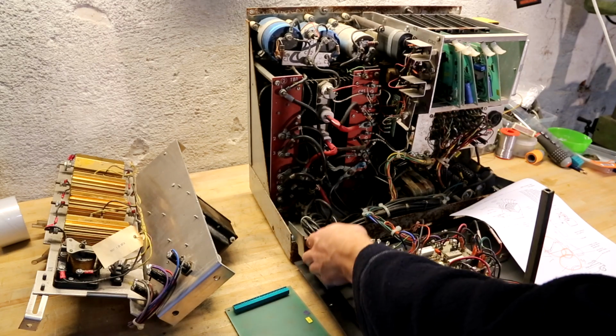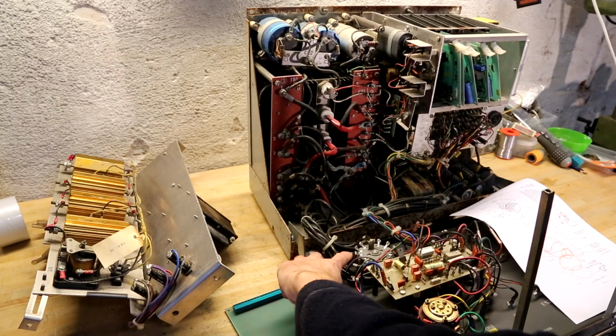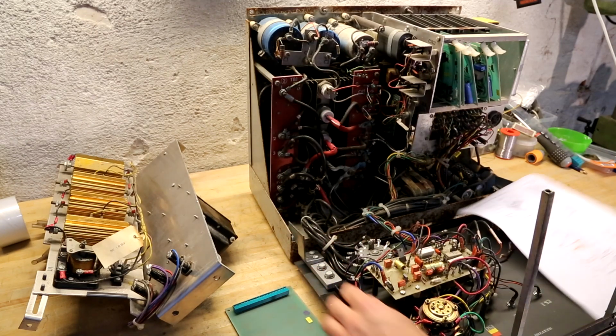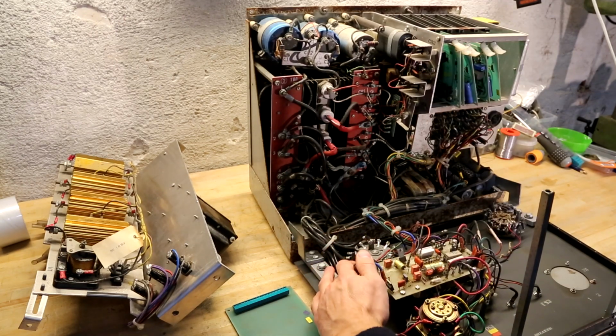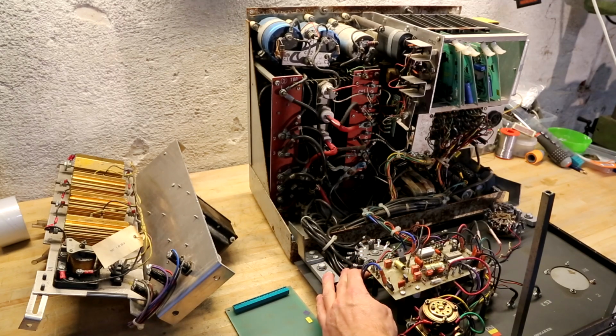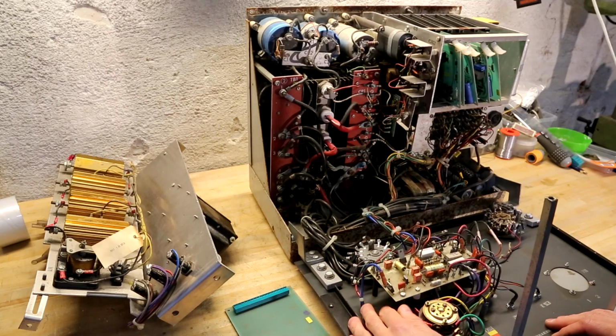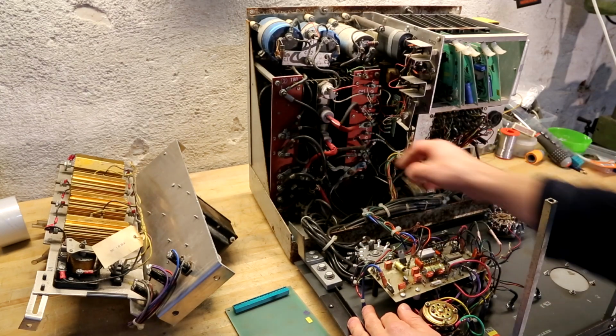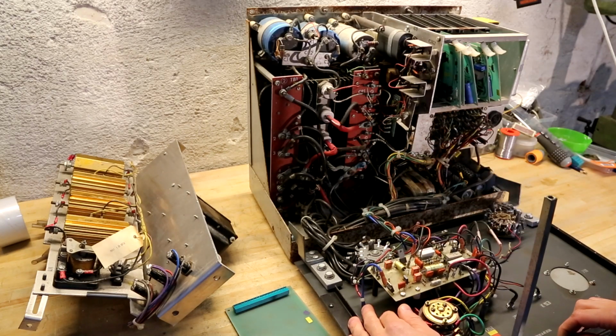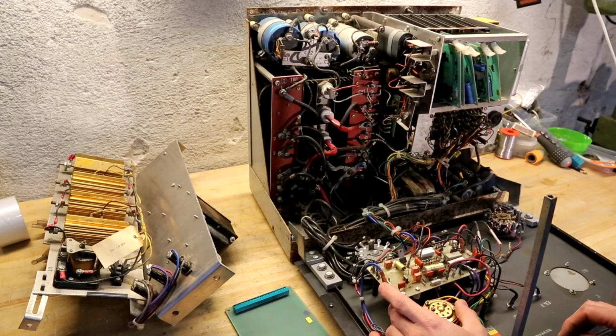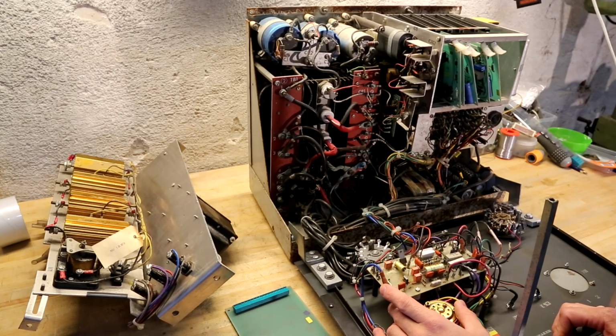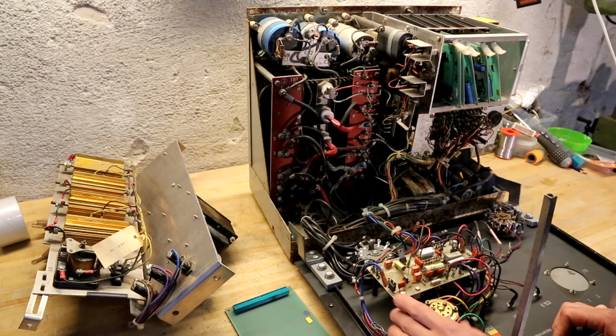And as we can see down here, there's this huge selector switch for the kilovolt peak. It is actually just running back into a huge transformer sitting in here at the back. So that's probably just running through a tapped transformer. So yeah, you can say clever. But back when you only had SCRs and you could drive them in a certain way, it's not that nice a square wave or something like that you drive them with.